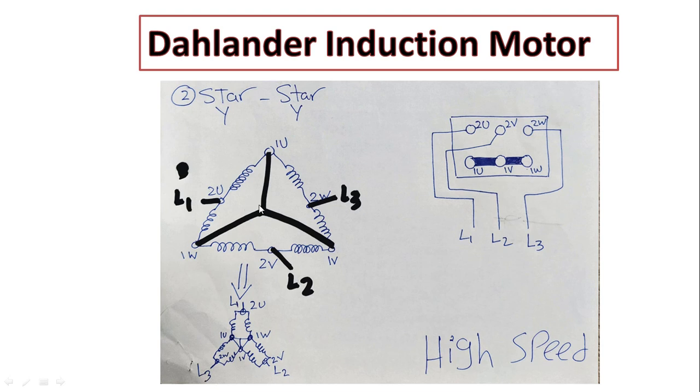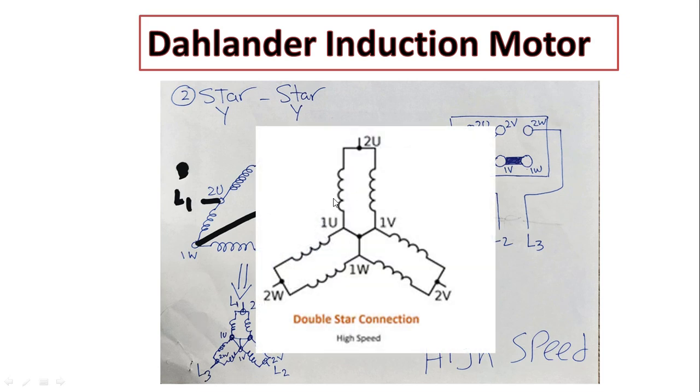Also we will connect 1U, 1V, 1W together as one point. So as you can see, inside the junction box we will connect L1, L2, L3 to 2U, 2V, 2W, and we will connect 1U, 1V, 1W together. At this time we will get this shape. It's more obvious here - we have two parallel windings in a star shape, so it's a double star connection.